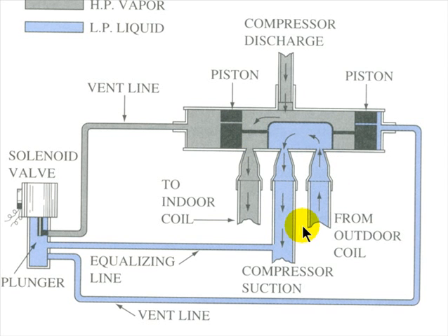So whenever I got a guy who brought back, when I was in wholesaling, a reversing valve from a brand new heat pump saying, this piece of junk, the heat pump went bad, we would either expect to see where he had completely overheated this thing and distorted this tube, or if the tube looked good and it was installed correctly, we could be guaranteed, especially on a new unit that he didn't have to install, that he was probably low on gas and that's why it didn't slide. It had nothing to do with the actual operation of it. And we used to actually have a little pool going to figure out how long it would take the guy after he left the shop with a new reversing valve to get back, reinstall the reversing valve, and get the thing running again to realize he was, in fact, short on gas.